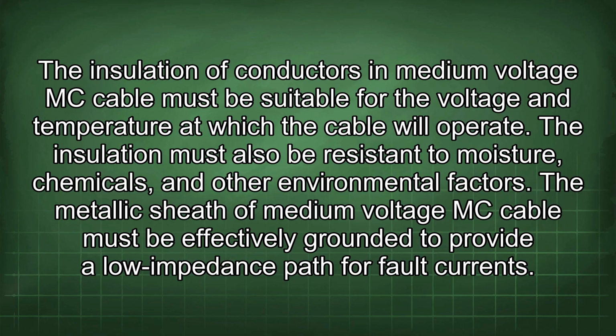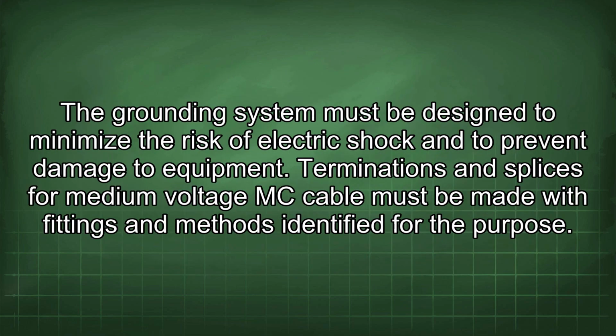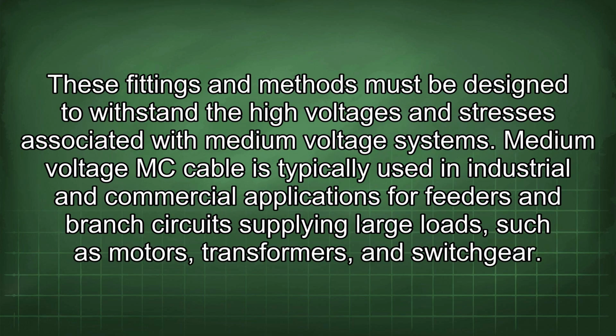The insulation of conductors in medium voltage MC cable must be suitable for the voltage and temperature at which the cable will operate. The insulation must also be resistant to moisture, chemicals, and other environmental factors. The metallic sheath of medium voltage MC cable must be effectively grounded to provide a low impedance path for fault currents. The grounding system must be designed to minimize the risk of electric shock and to prevent damage to equipment. Terminations and splices for medium voltage MC cable must be made with fittings and methods identified for the purpose. These fittings and methods must be designed to withstand the high voltages and stresses associated with medium voltage systems.